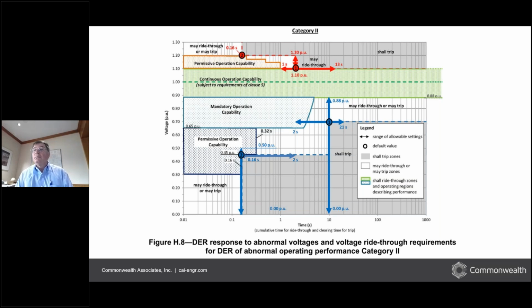We'll show some examples later on, but along with that, we have areas of shall trip. We get into areas where there could be a danger or a risk to the equipment. So we want to make sure that we get that equipment offline to not jeopardize the health of it. So these are very important.